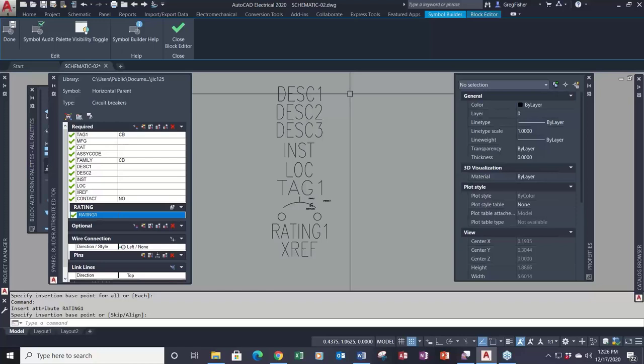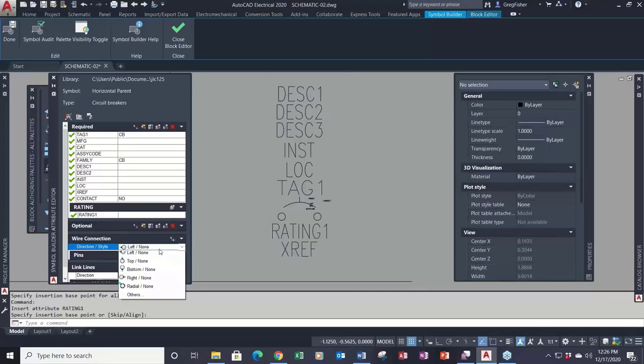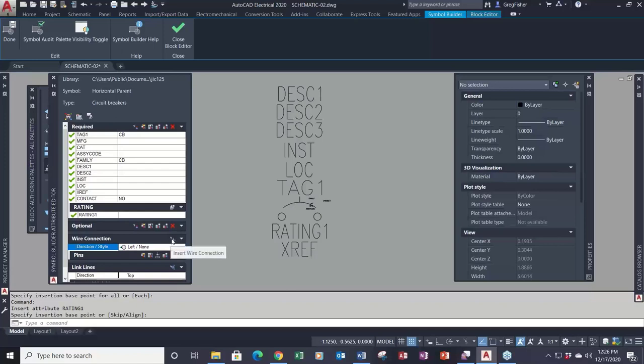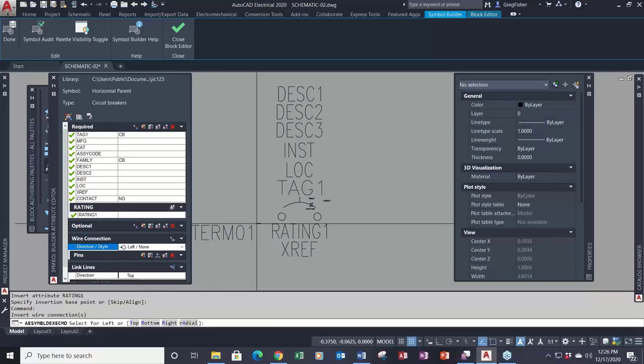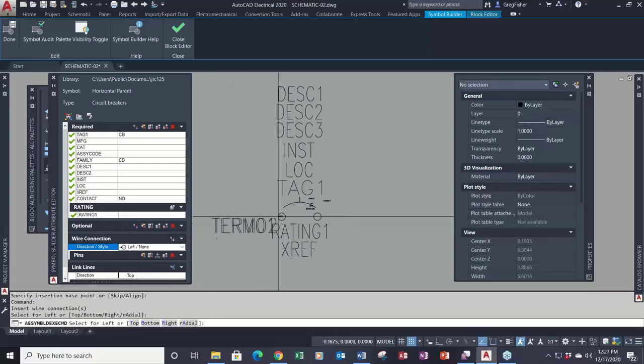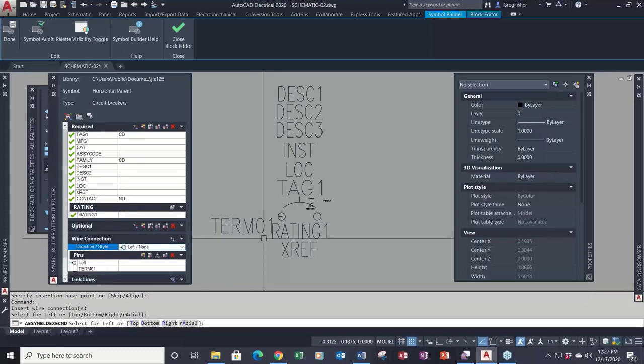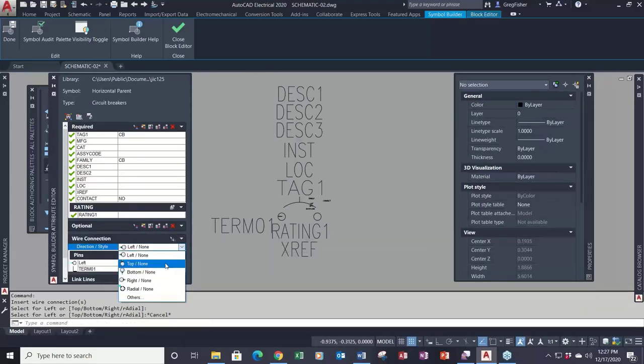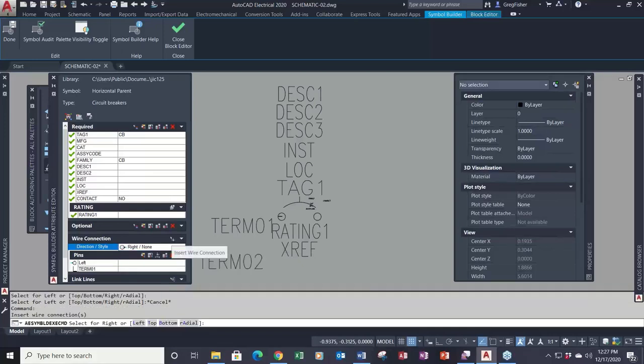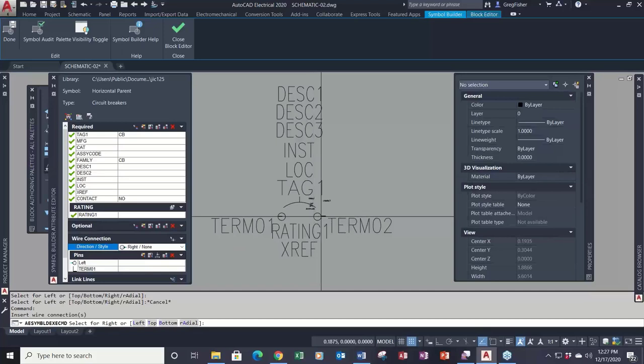I also have a rating attribute, so I'm going to insert one rating attribute and drop it down here. As you know when you insert a symbol in AutoCAD Electrical, you have the tag, three lines of description, installation, location, and rating — all the attributes placed down. I have to use their defined tag names; I can't just make up my own, it won't work that way.